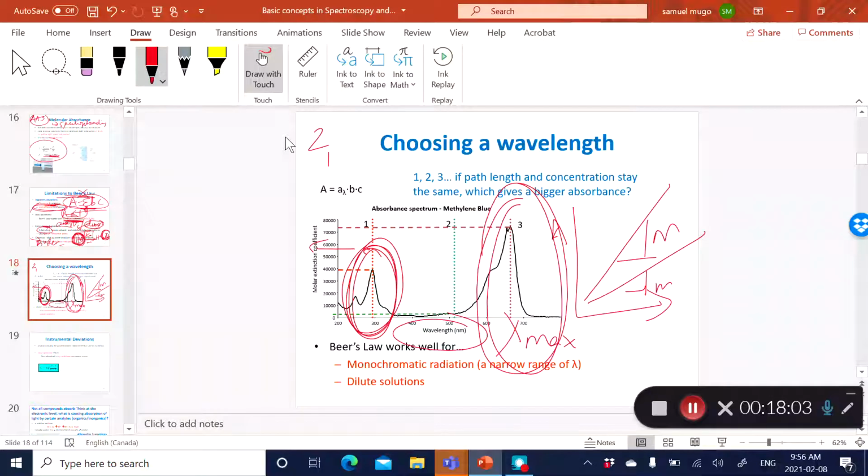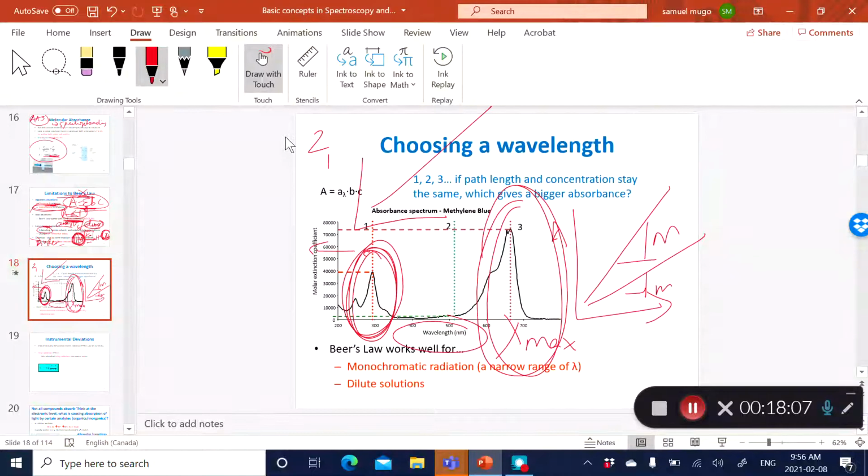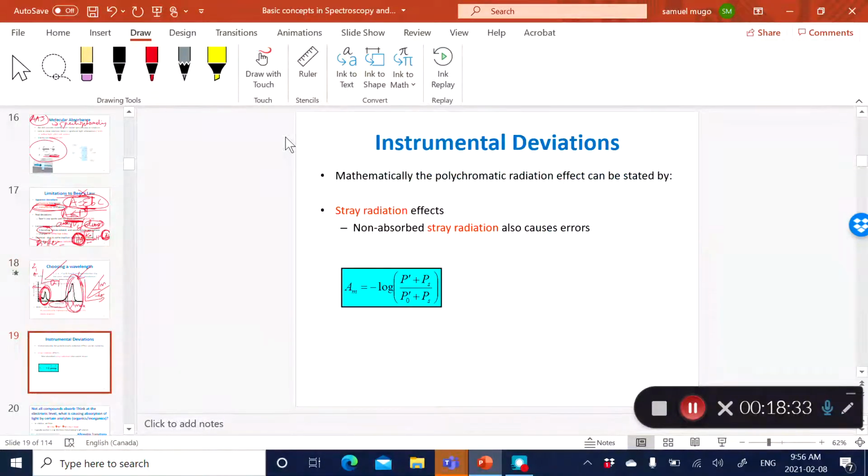And so that one is going to help you not dilute the samples, and equally, of course, you're going to have a linear relationship. So that's the other approach that you can use if you do not want to dilute the sample. The challenge with that, of course, is that you'll be affecting your sensitivity, because sensitivity is greatest at the wavelength of maximum absorbance.